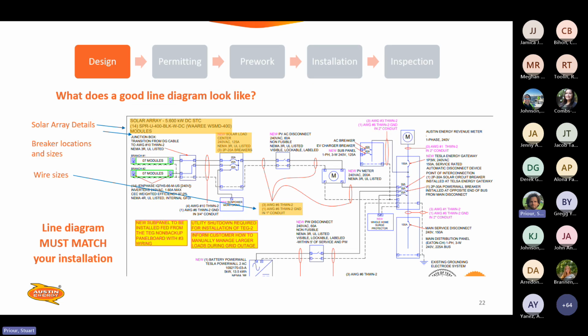So what does a good line diagram look like? You can see here, this has plenty of detail as far as the make and model of inverters. It's got all your proper wire sizing and wire types. It's calling out all components like junction boxes in between the array and aggregate panels. Your overcurrent protection is called out. You've got line to load called out properly on the solar meter.